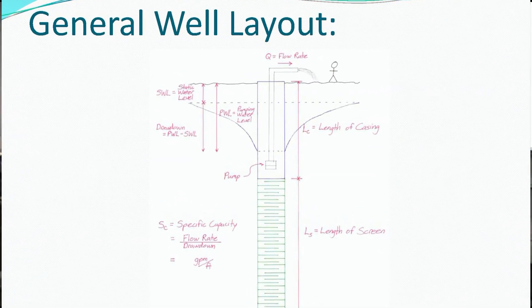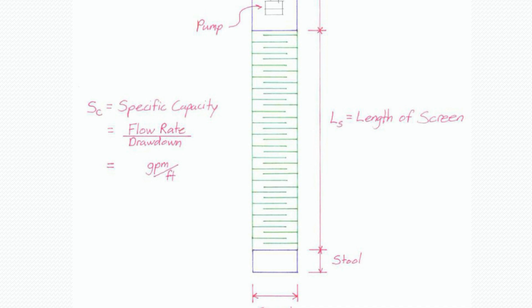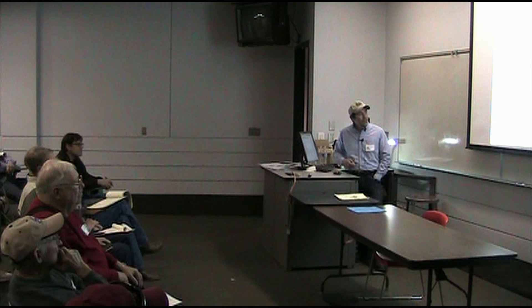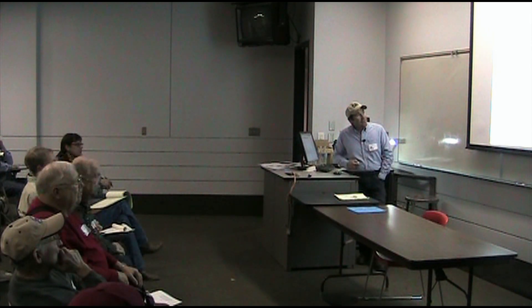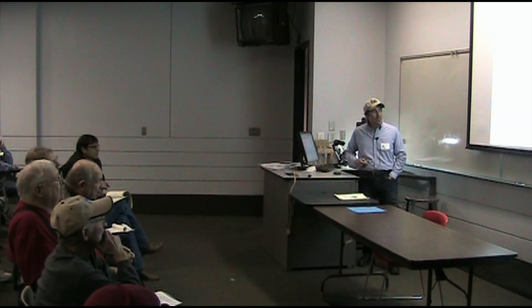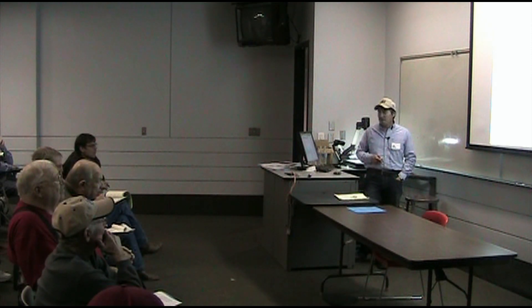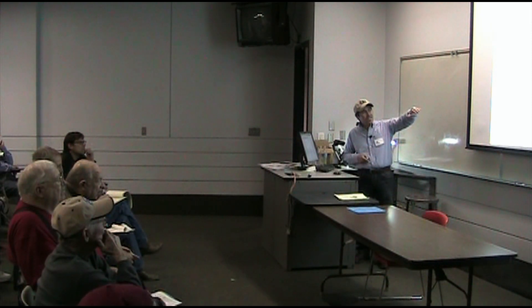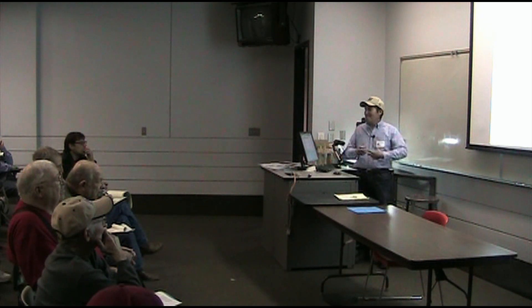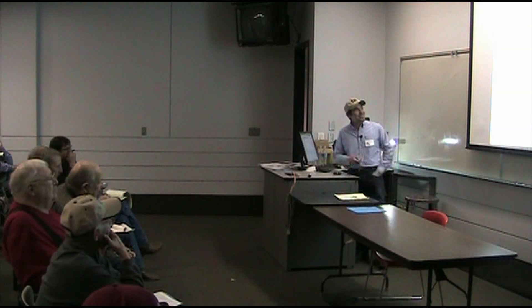The general layout of a well has the casing portion on top followed by a screen portion, and I like to put a sump at the bottom so any sand that comes in stays there rather than plugging up the screen. We want the pump inside the casing — the casing should encase the pump. The pump should be up in the casing to avoid sand pumping. If the pump is down near the screen it'll concentrate suction in a small region, drag sand into the well, wear out your pump, and start filling the well with sand — creating a vicious cycle.